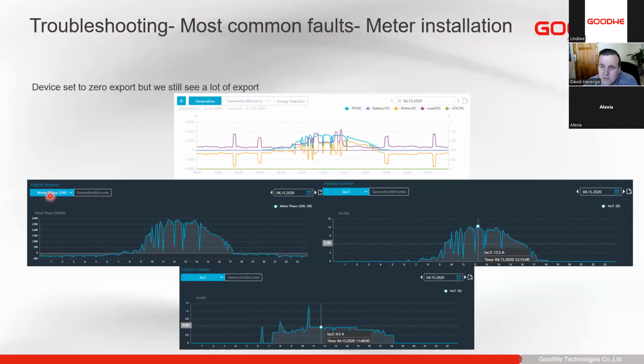to find the meter. Phase 2 was showing all our export. So then I went to look at IAC2. On IAC2, there's no notable AC output from the inverter, but I found on IAC3 that export is on IAC3. So what this means is our smart meter thinks it's on AC2, so that's why IAC2 is not producing anything, but it detects usage on phase 3. So phase 3 is producing as much as it can, but it can't negate that usage, and this results in export, because it reads the export on phase 2, but it's producing it on phase 3.